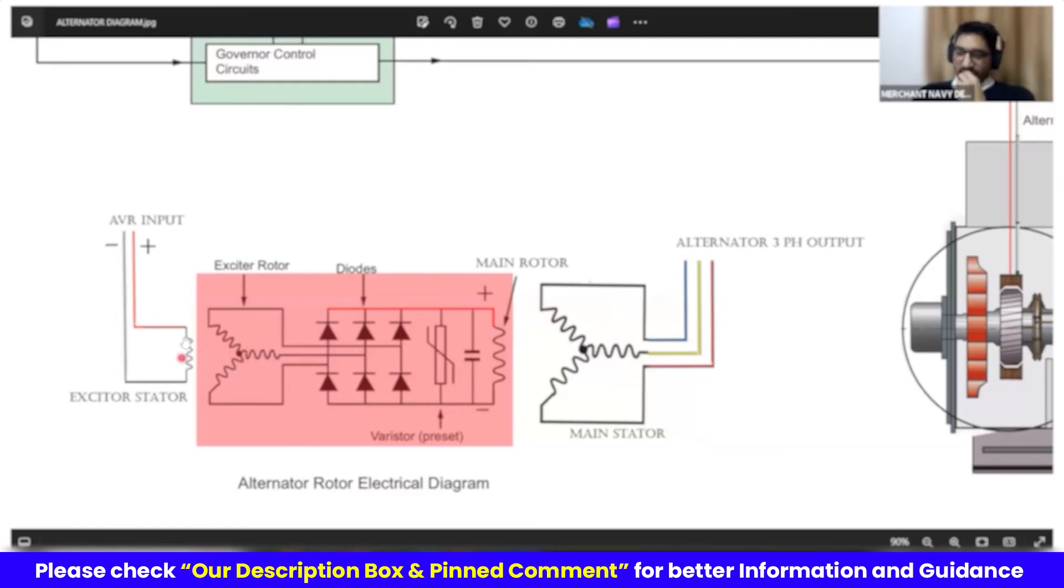This magnet, electromagnet will produce AC here, three phase AC. This three phase AC needs to be rectified by three phase rectifier. This is nothing but three phase rectifier. This is also rotating. This is also called RRA, rotating rectifier assembly. And it is now rectified to a DC current, plus and minus.